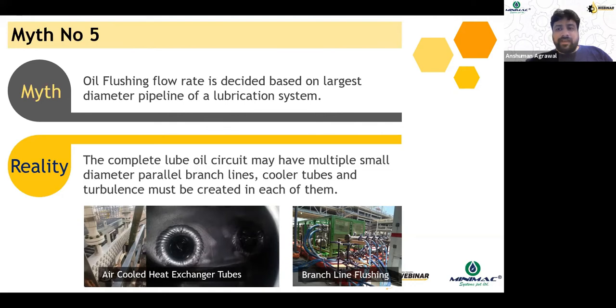What actually happens is your flow rate gets distributed into multiple loops, the branch lines and the manifolds. So when you decide a flushing flow rate, you need to check each of the branch lines. You need to check if you have some cooler tubes or some heat exchangers. You need to check the flow rate through each of the tubes. And only then can you decide the flushing flow rate.